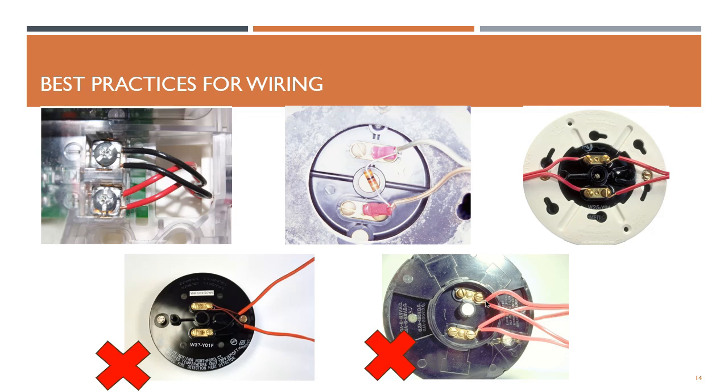Further to the right, we have devices in the middle of a loop with cables that come in as well as cables that come out. Now, it's strange because in this connection we see two red wires when it should be red and black. The main purpose of the picture was to demonstrate how to get in and exit from a device. Below we can see the incorrect ways.